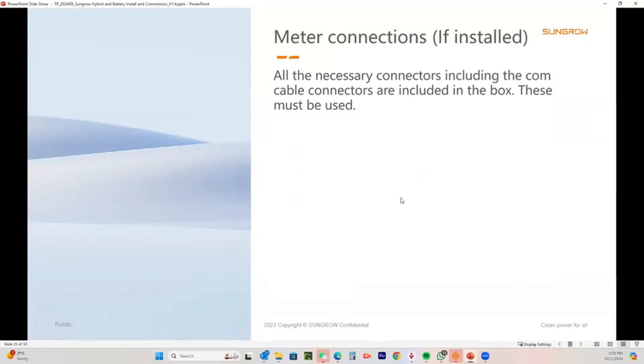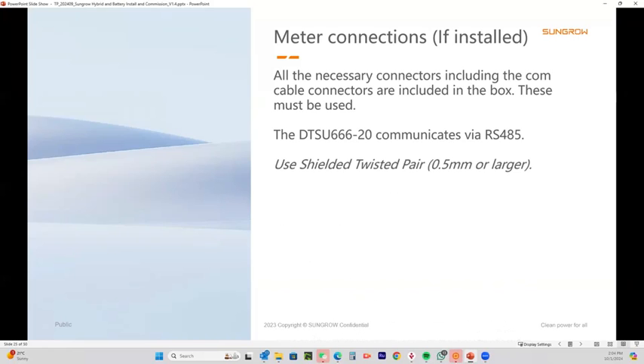Okay, meter connections. All the necessary connections, including the COM cable, are included in the box. Now you must use the stuff, if possible, that we supply. I think the meter cable is supplied at about 8 meters. If it is longer, you're going to have to purchase some cable for that. Now, the meter always communicates via RS485. RS485 is a specific data protocol, and there is actual RS485 cable, which is shielded twisted pair. Always use that, 0.5 mil or larger cross-sectional area. A lot of people like to use Cat6. Yes, it can work to a degree, but it's not quite the correct cable, and you may get problems with communications. Really seriously, purchase and use the proper shielded twisted pair cable.